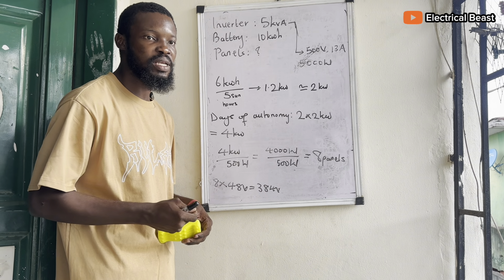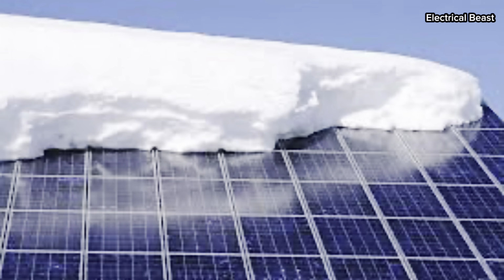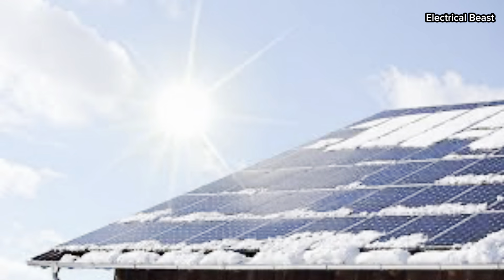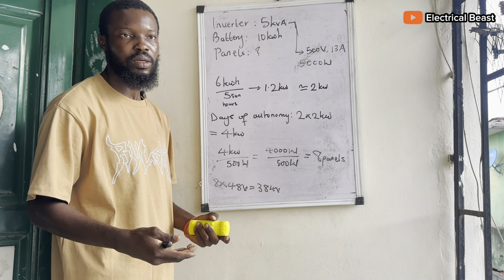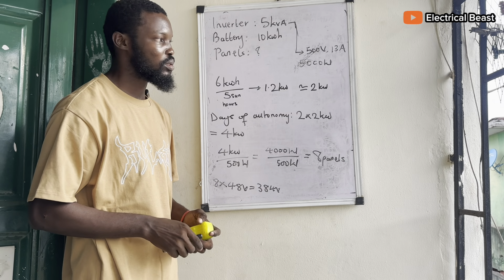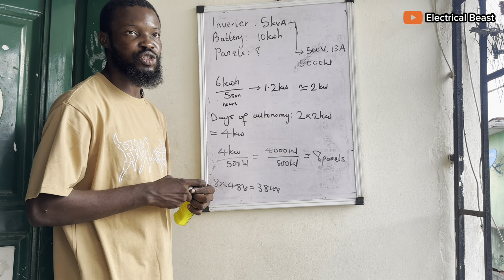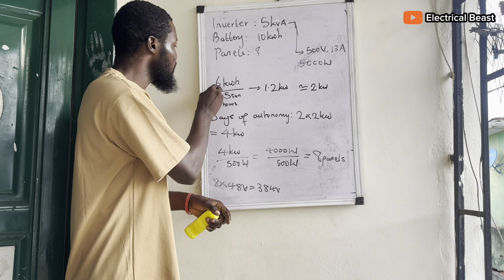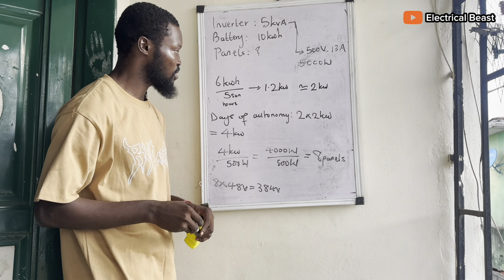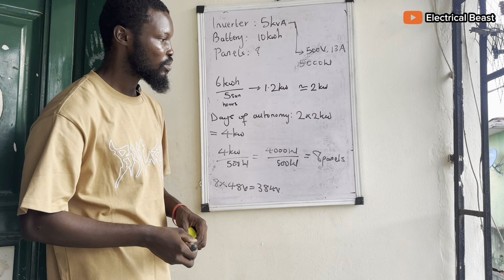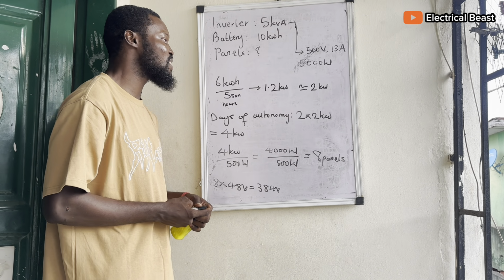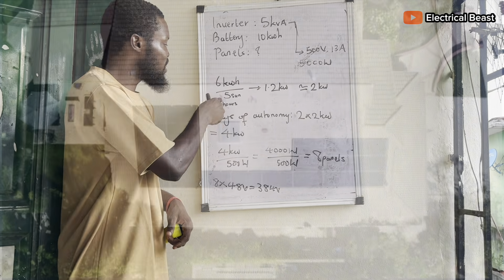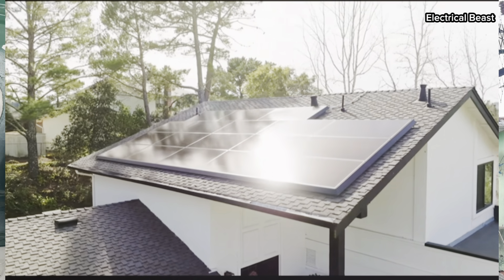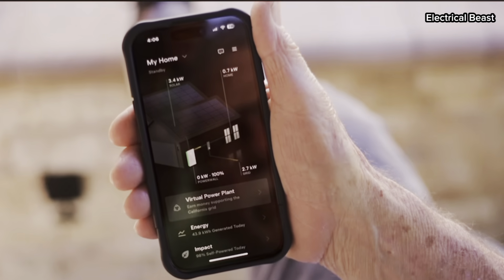Now, there's what we call sun hours. It differs. It depends on your location. So there are some locations that have just 1 hour of sun for the entire day. Some not even up to 1 hour. Other locations have 8 hours of sun, depending on where you are. So let's use an average of 5 sun hours. Now, the total daily energy consumption is 6 kilowatt hour. So when you divide 6 kilowatt hour by 5 sun hours, you have 1.2 kilowatts. Now, your panel should be able to generate at least 1.2 kilowatts within this amount of sun hours because that's when the sun is at its peak. Now, when you have this, let's just approximate to 2 kilowatts.